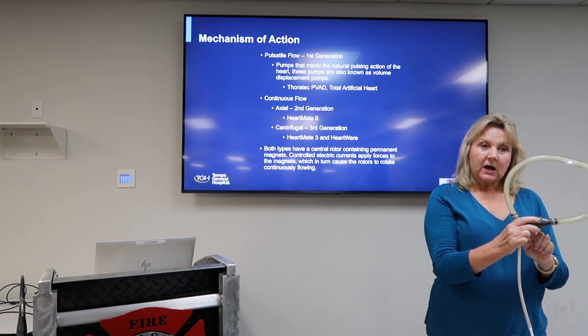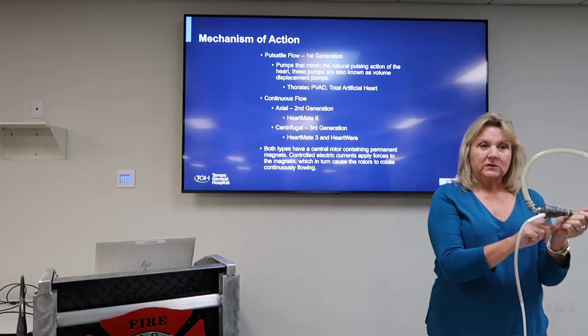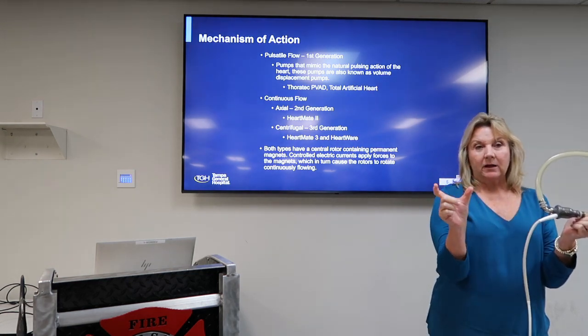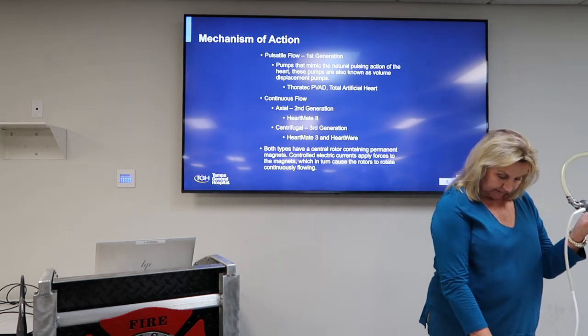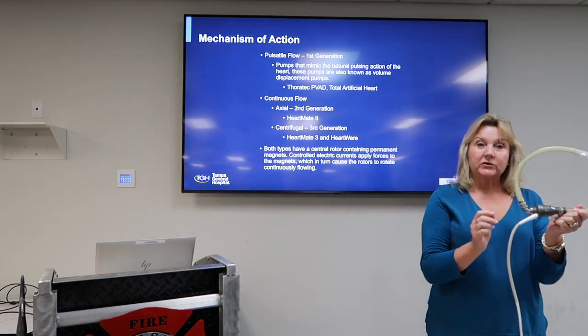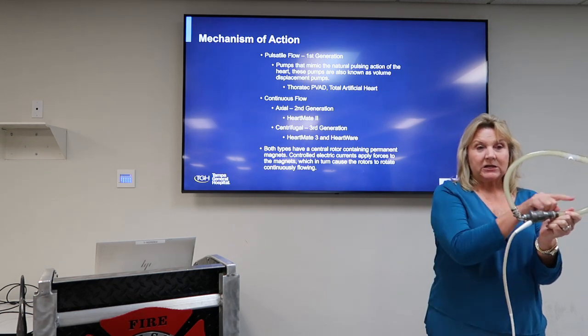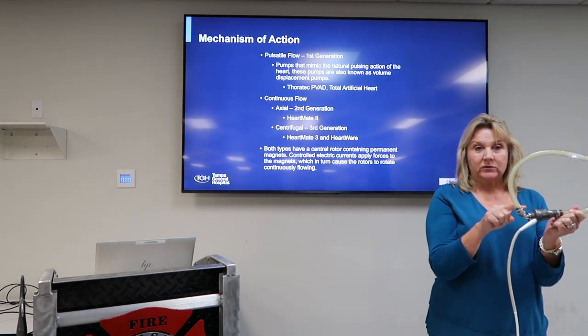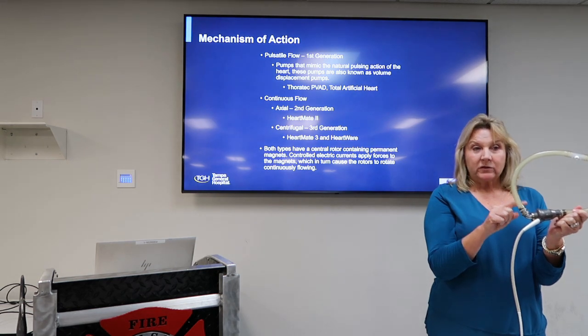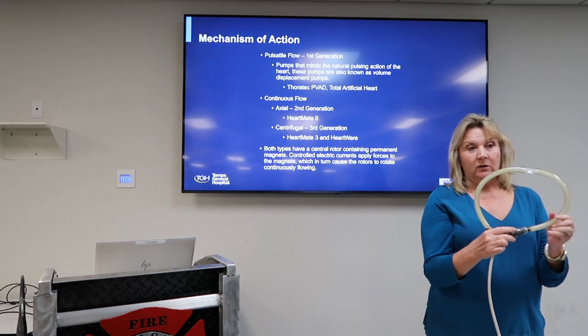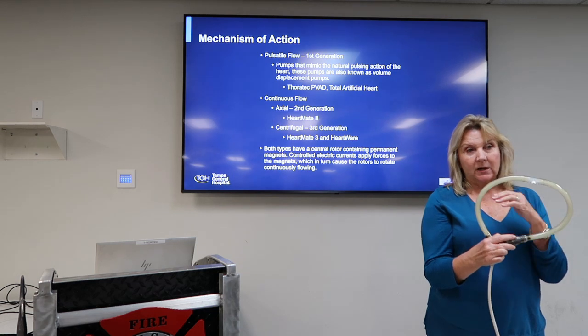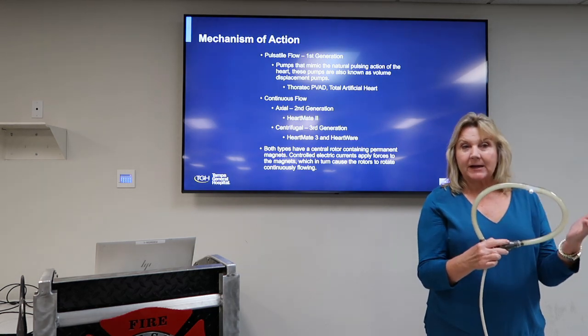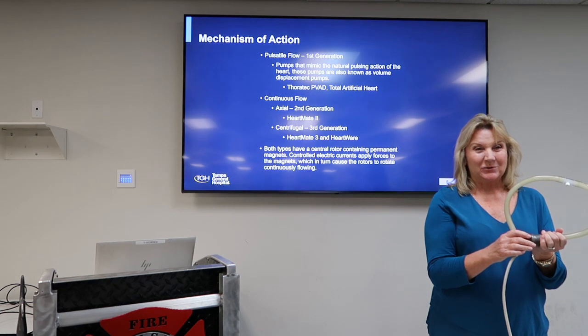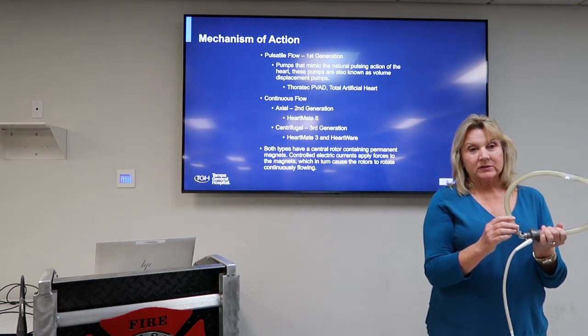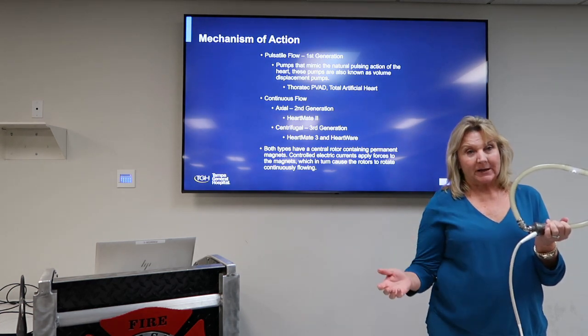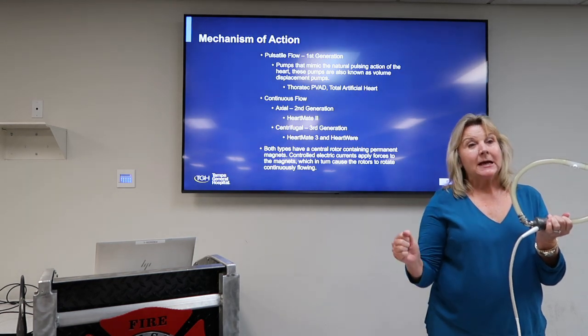So if you did a cutaway of this device, inside is an impeller that's spinning right now about 9,400 times a minute. So it's continuously pulling blood around and around. With that particular design, you're not made to work with continuous flow, so there are some problems that can occur because of continuous blood flow as opposed to pulsatile.